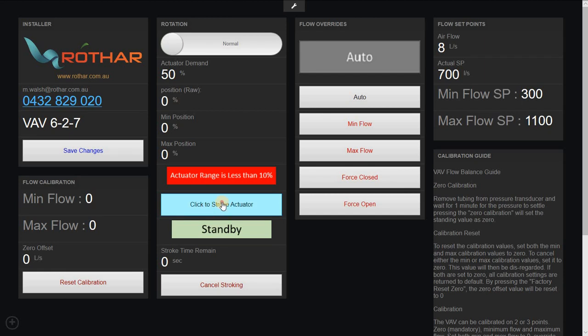So if you click the stroking, it will change from standby to stroking and go to predetermined stroking time and count down to 0. It will then reset to stroke the other way. That way you can see what's going on. If the actuator is not driving or if your feedback's not changing as expected, you can cancel the stroking, make your changes and retest the actuator. So the balancing guys may want to force to max flow or maybe force it open, which you can do from here.